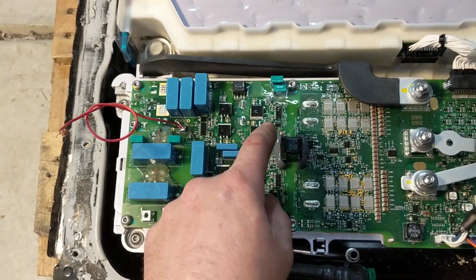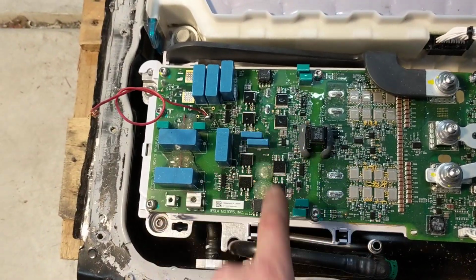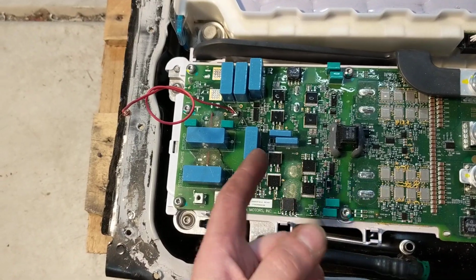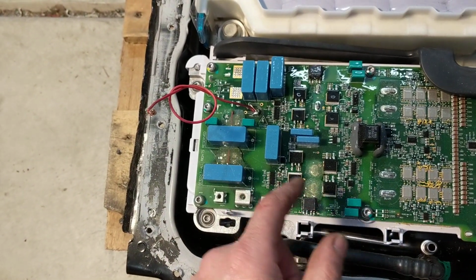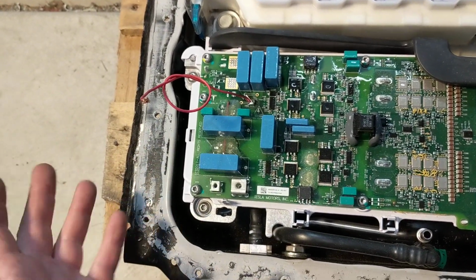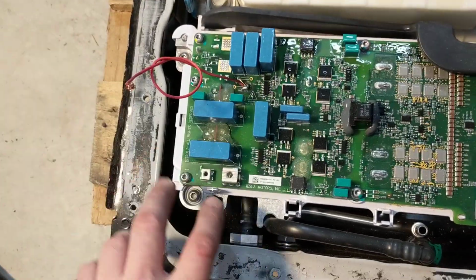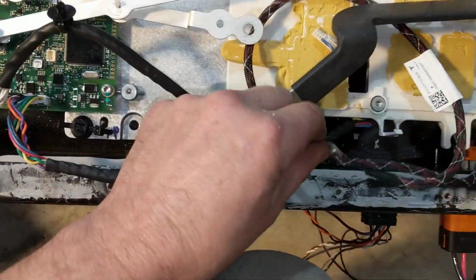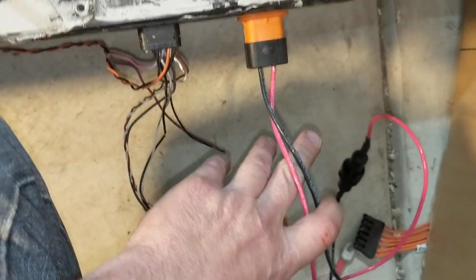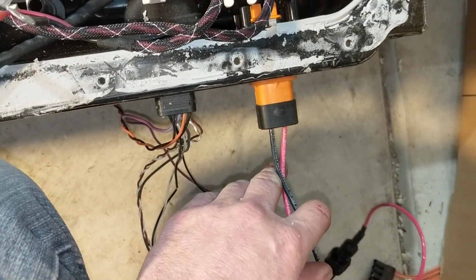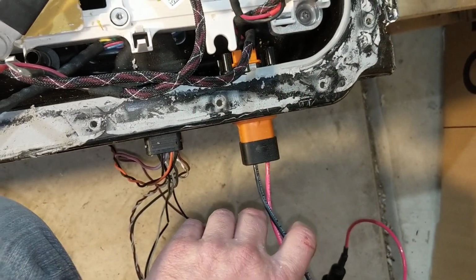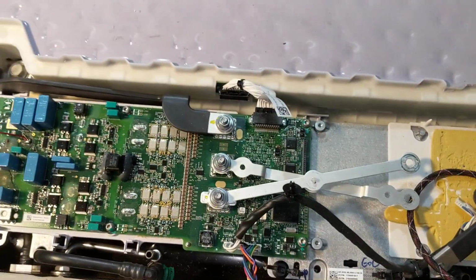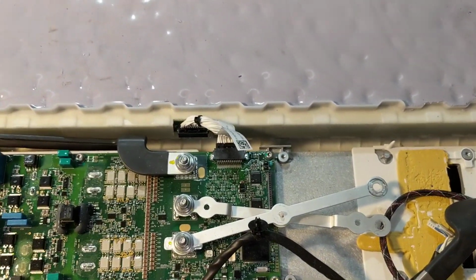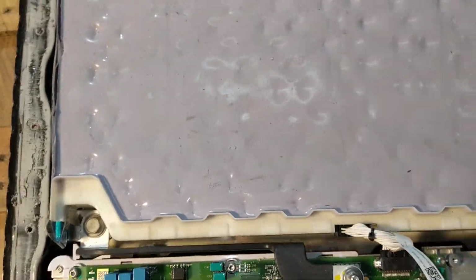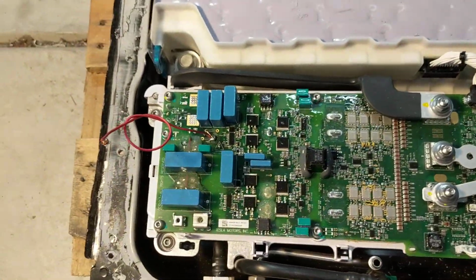The 400 volts DC is then either wired in series or parallel, depending on the cabinet. I suspect they're all series now, so that produces about 800 volts DC, which normally comes off terminals I've got disconnected, and goes here. These are in a bus configuration from module to module, so only one module can keep a whole cabinet running if all the others were to fail. They're not wired in series or anything from module to module.